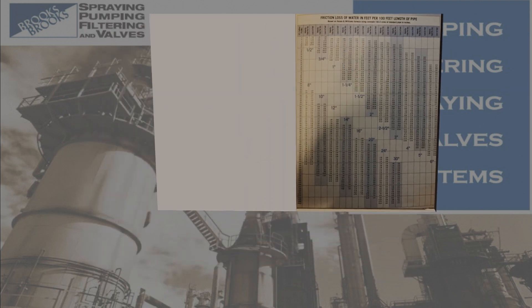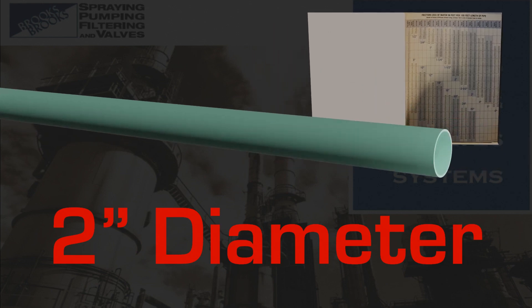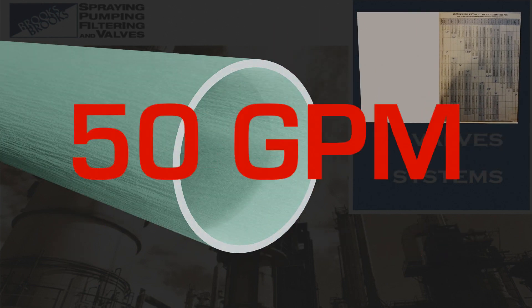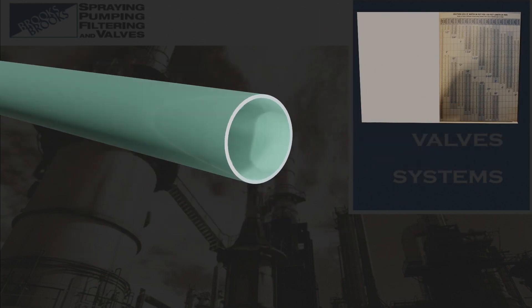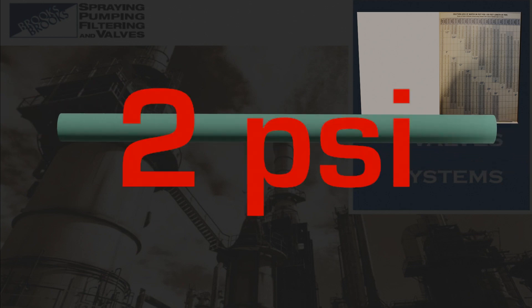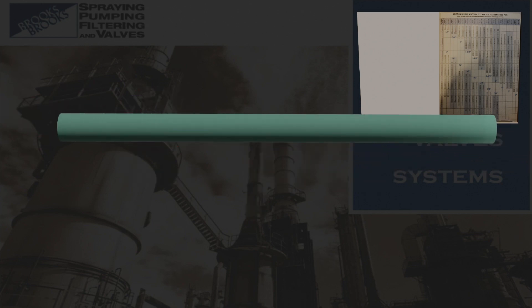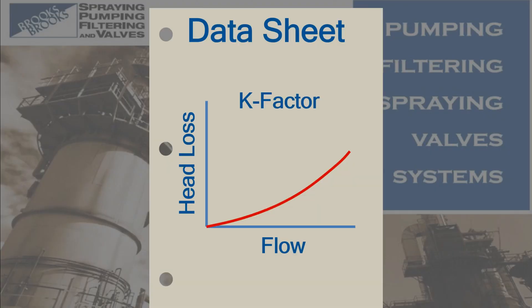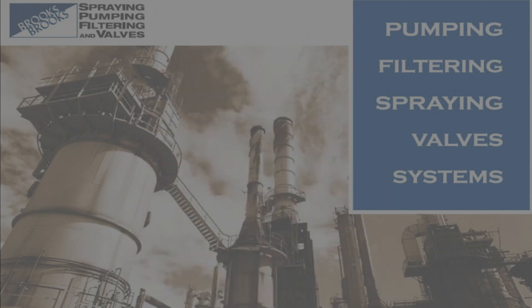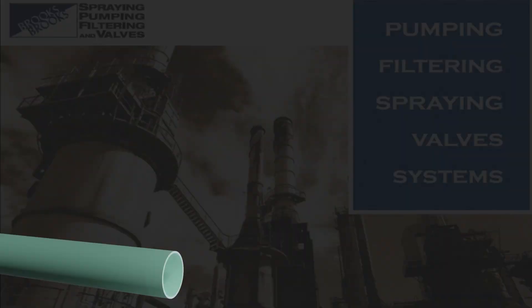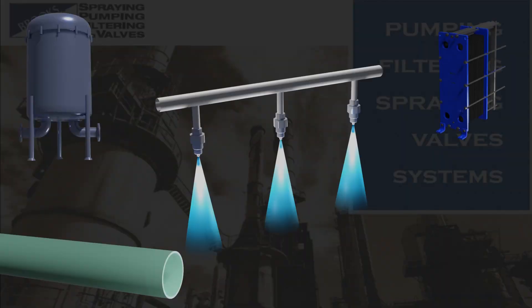By referencing commonly available tables, we can find that a 100-foot-long, two-inch diameter steel pipe with 50 gallons per minute of water flowing through it has a frictional loss of about 2 psi. As we increase this flow rate, the losses will also increase. Similar relationships can also be found for the other components in the piping system.